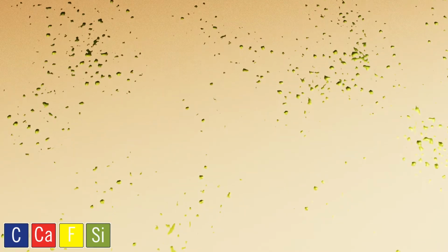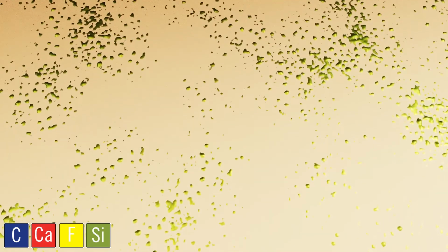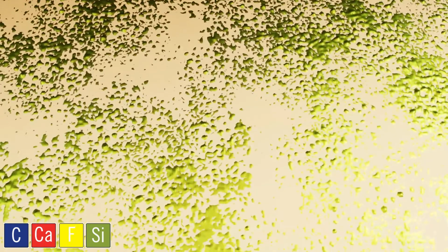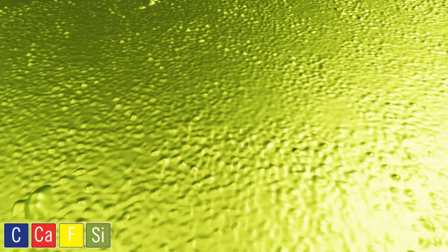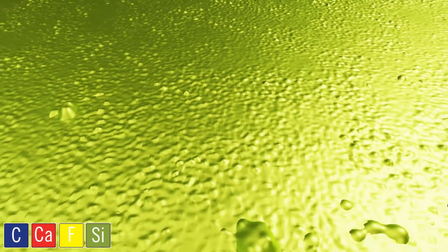This is a new membrane. As pure water is being removed from the feed stream, sparingly soluble salts become more and more concentrated. If the salts reach a point of supersaturation and overcome the additional protection of any online antiscalants, they may precipitate onto the membrane surface in what we call scale, blocking permeate flow. Silica deposits in a very thin layer on the membrane.